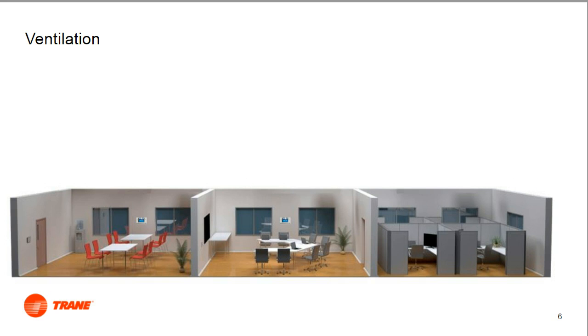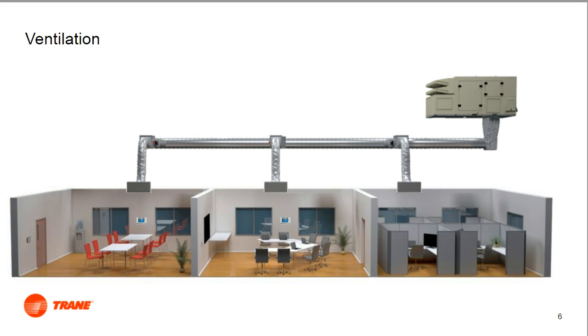The second subsystem is the ventilation system, which could be a dedicated outdoor air system, or DOAS for short. It is made up of a 100% outdoor air unit that conditions and ventilates air before delivering it to the zones. There are numerous ways to address the outdoor air treatment, and I will discuss them more in detail. The ventilation system includes ductwork and the outdoor air room diffusers to deliver the ventilation air to the zones. This DOAS also provides demand control ventilation with the addition of pressure-independent variable air volume diffusers. The final subsystem is the controls.